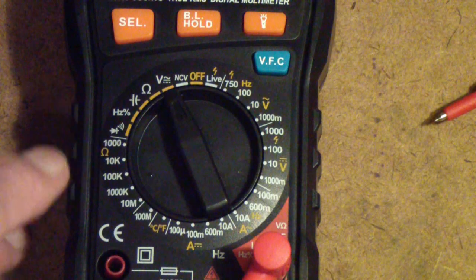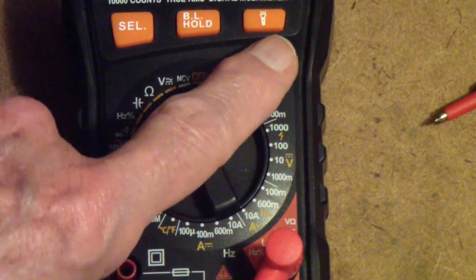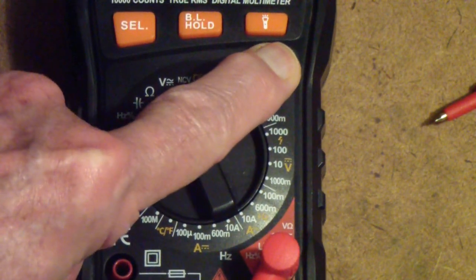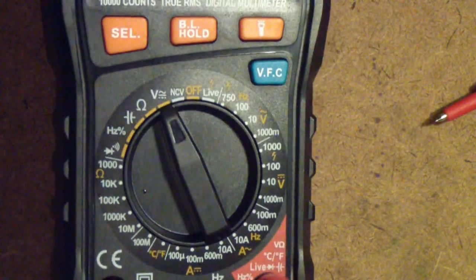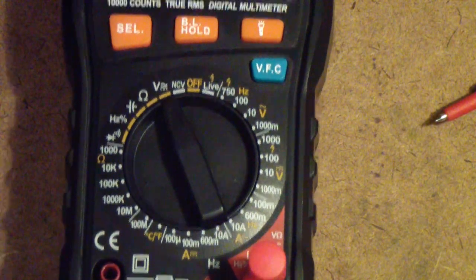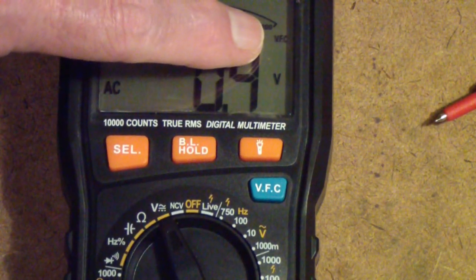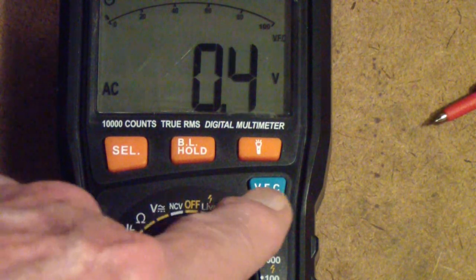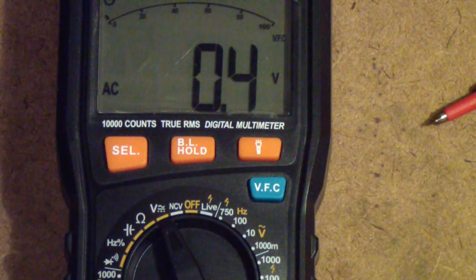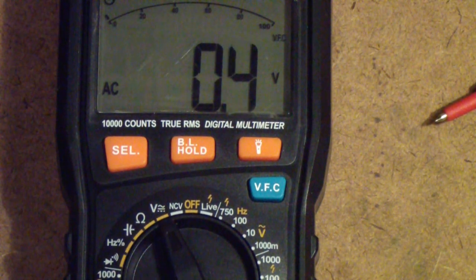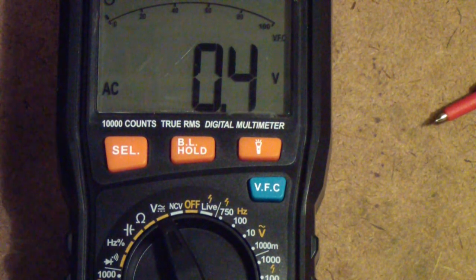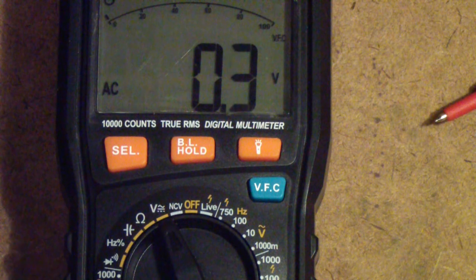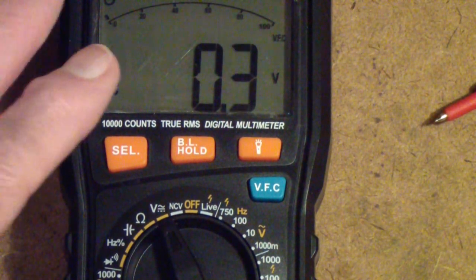So I'm going to go here to AC and then I'm going to hold this down. You notice—I don't know if it shows up very well—that VFC shows up in this upper part of the display. What that tells you is this low-pass filter has been inserted. The low-pass filter gets rid of all the high-frequency harmonics that tend to cause the erroneous readings and focuses the meter on the low-frequency which is what is actually producing torque in the motor.